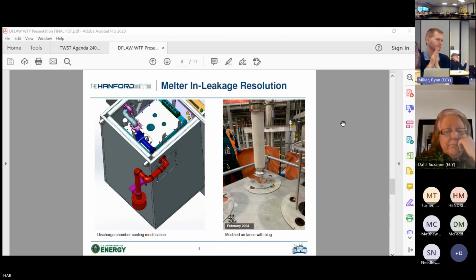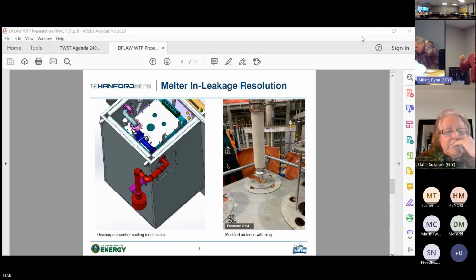Just a comment, Matt, could you comment on the idea that what you're looking for is balanced airflow, not too little, not too much? Yeah, so the facility was designed so the plenum is at nominally -5 inches with a particular flow that goes with that -5. So that's a good reinforcement of why, although we could get to -5 before we put that plug in, it was at a much higher flow rate.